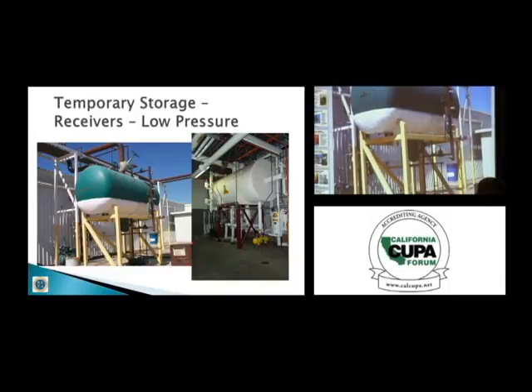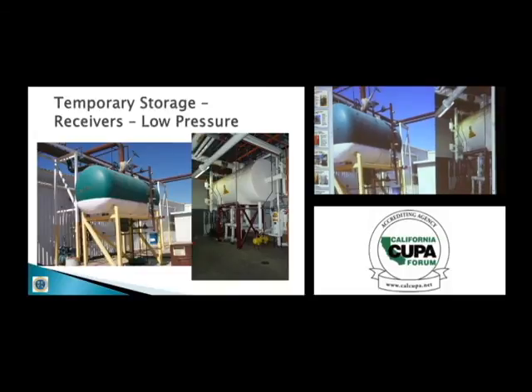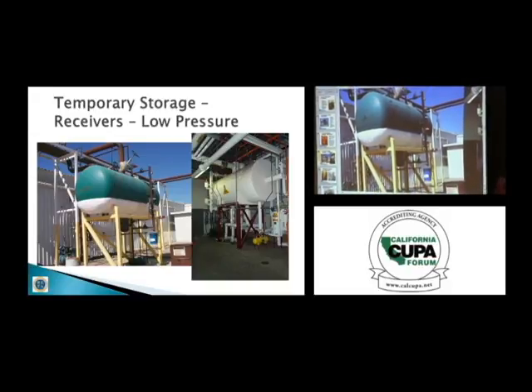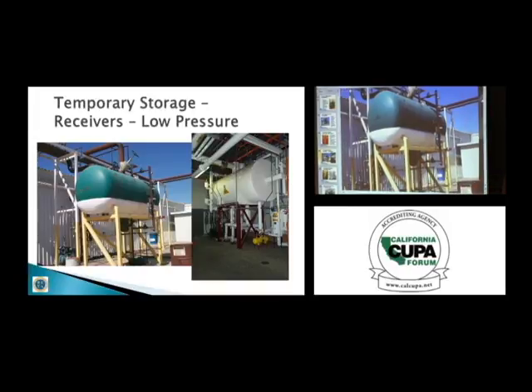If you can go to zoom, and if that was 250 or 200, go to like 160. Okay, so we're looking at this. This is not in any of your jurisdictions, by the way. Truly, it isn't. It is a suction accumulator, thank you. And so we have the frost line, we call those Casper tracks. See, because Casper, the friendly ghost, can go through walls and such. But when he goes through, if the air is carrying moisture, the moisture doesn't go through with him and it freezes out. That's a great operator tool.